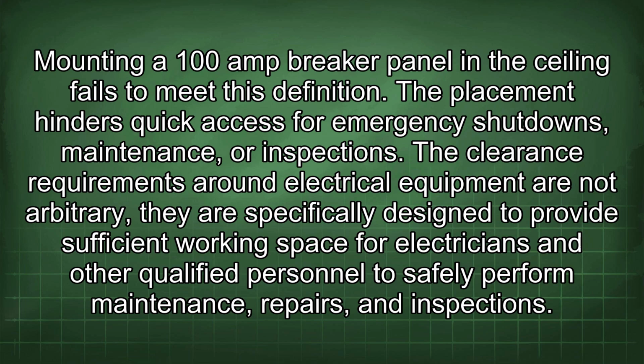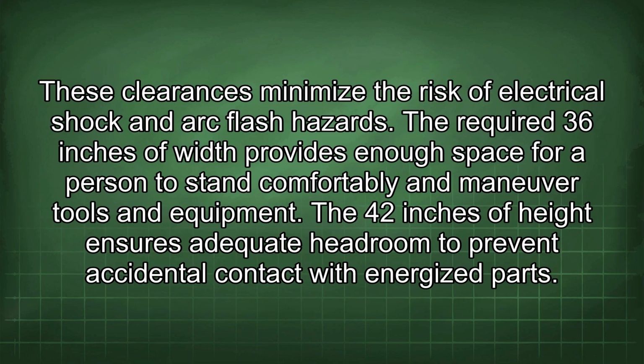The clearance requirements around electrical equipment are not arbitrary. They are specifically designed to provide sufficient working space for electricians and other qualified personnel to safely perform maintenance, repairs, and inspections. These clearances minimize the risk of electrical shock and arc flash hazards. The required 36 inches of width provides enough space for a person to stand comfortably and maneuver tools and equipment. The 42 inches of height ensures adequate headroom to prevent accidental contact with energized parts.